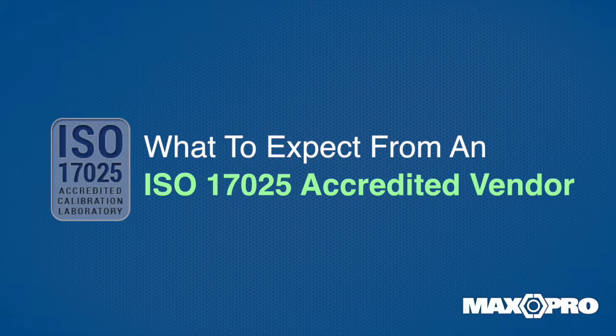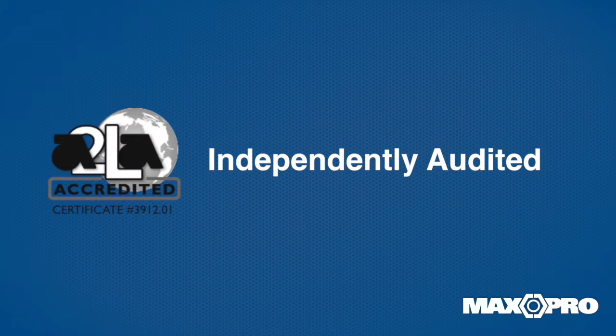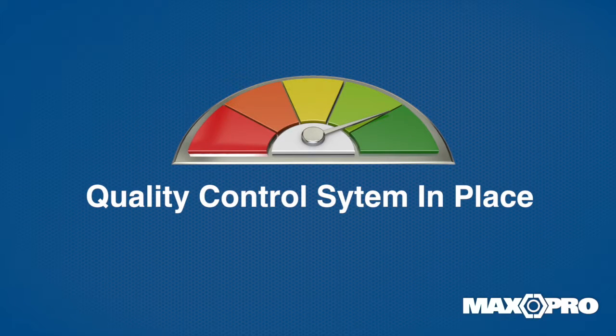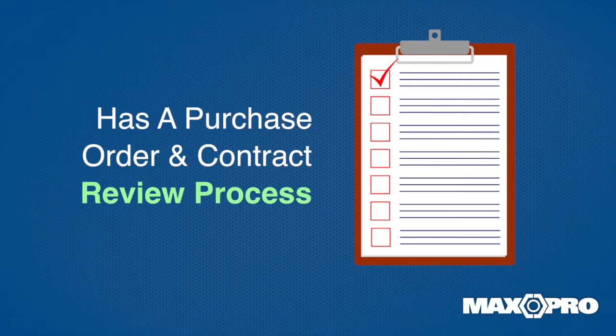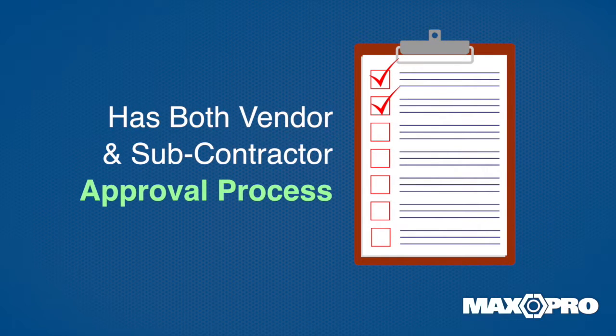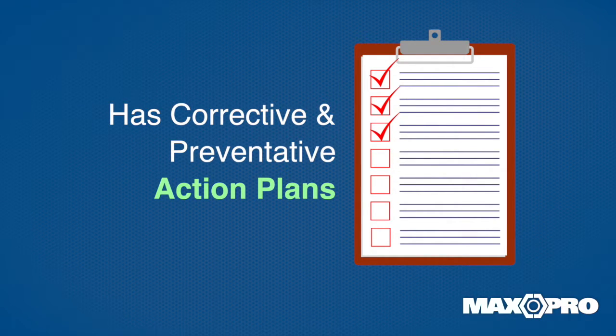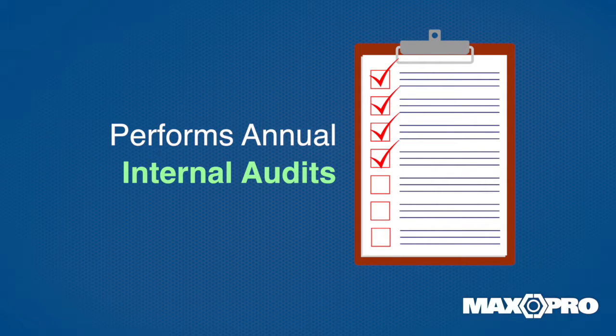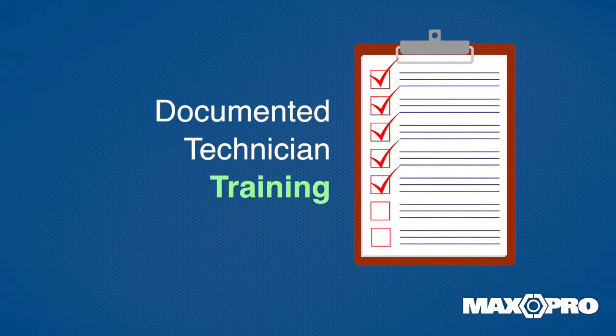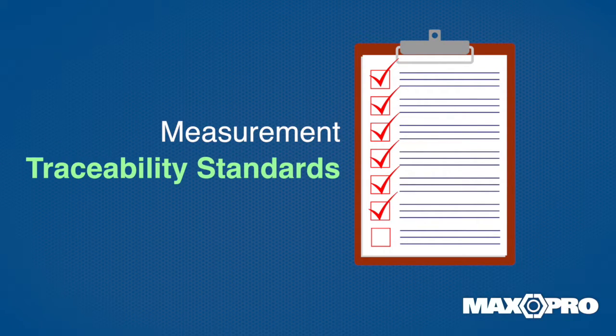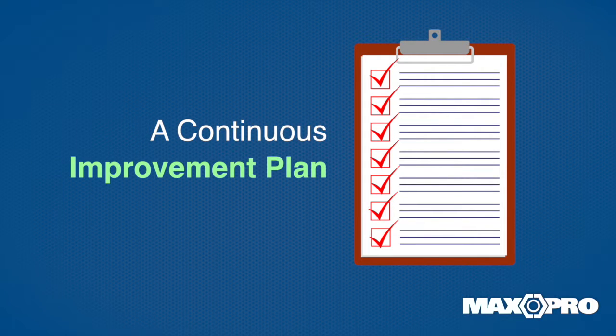An accredited ISO 17025 approved calibration lab offers the following: independently audited by an outside agency such as A2LA or A-Class, has a full quality control system in place, utilizes a purchase order and contract review process, uses a vendor and subcontractor approval process, has corrective and preventative action plans, completes annual internal audits, has documented technician training on the products to be calibrated, measurement traceability standards, has a continuous improvement plan.